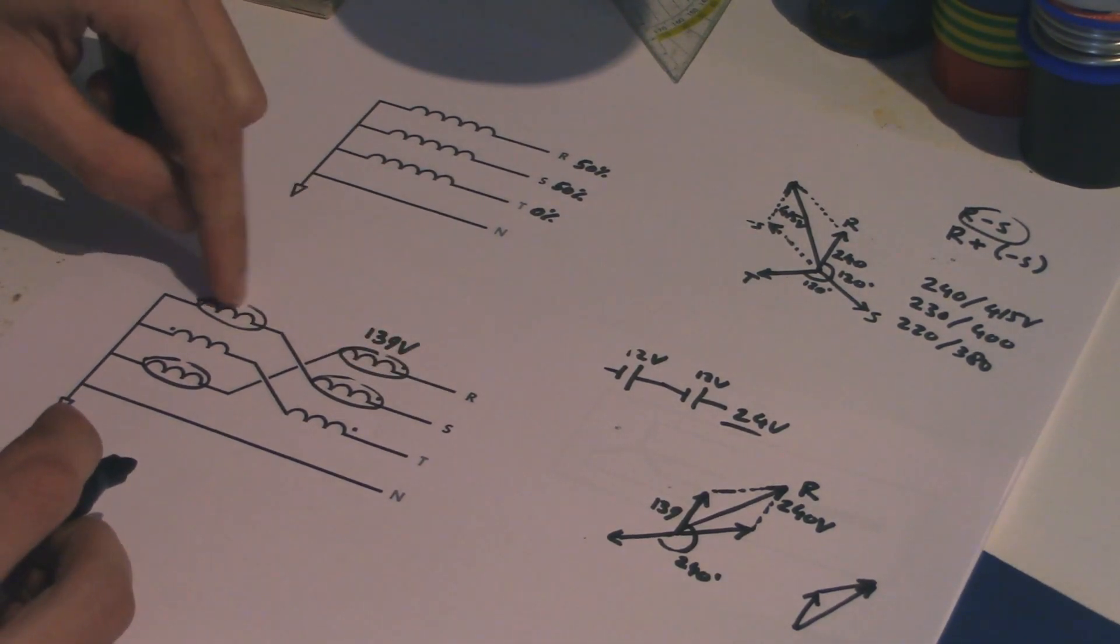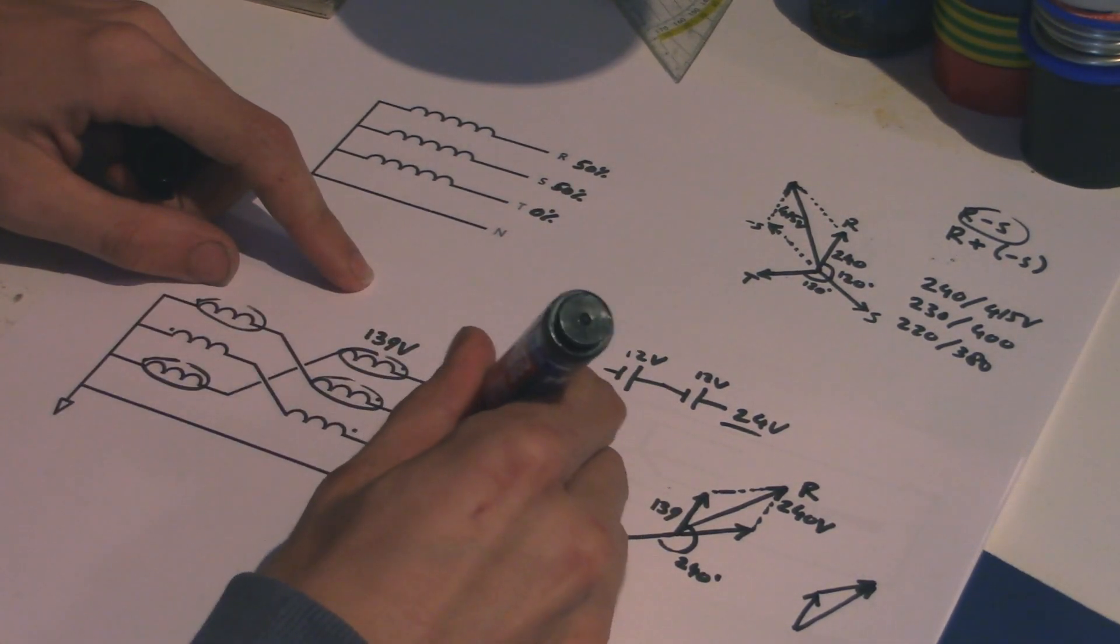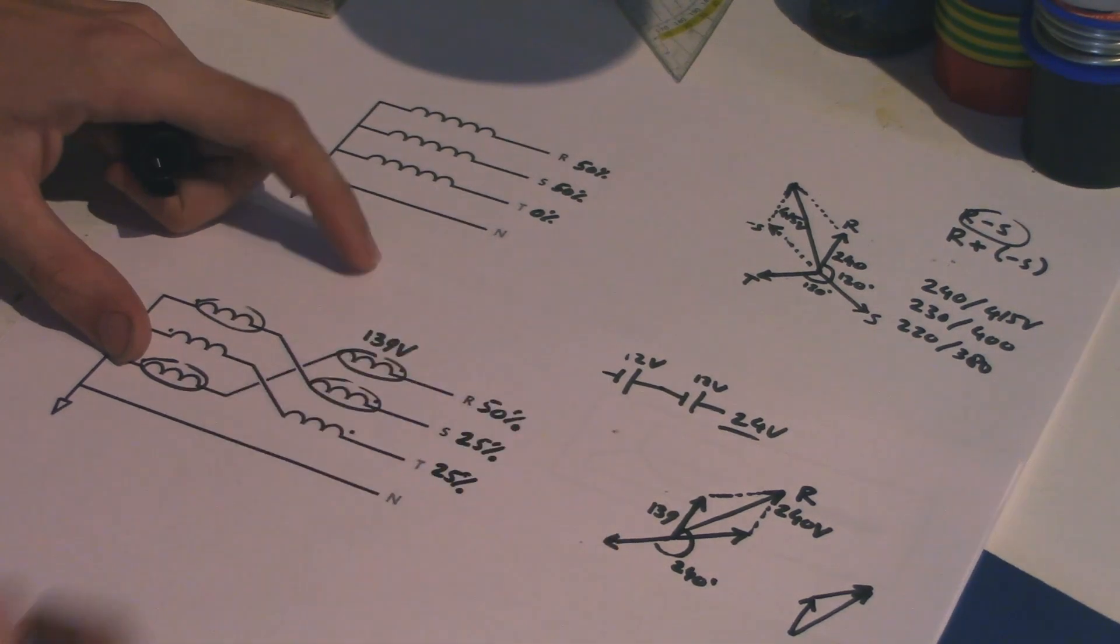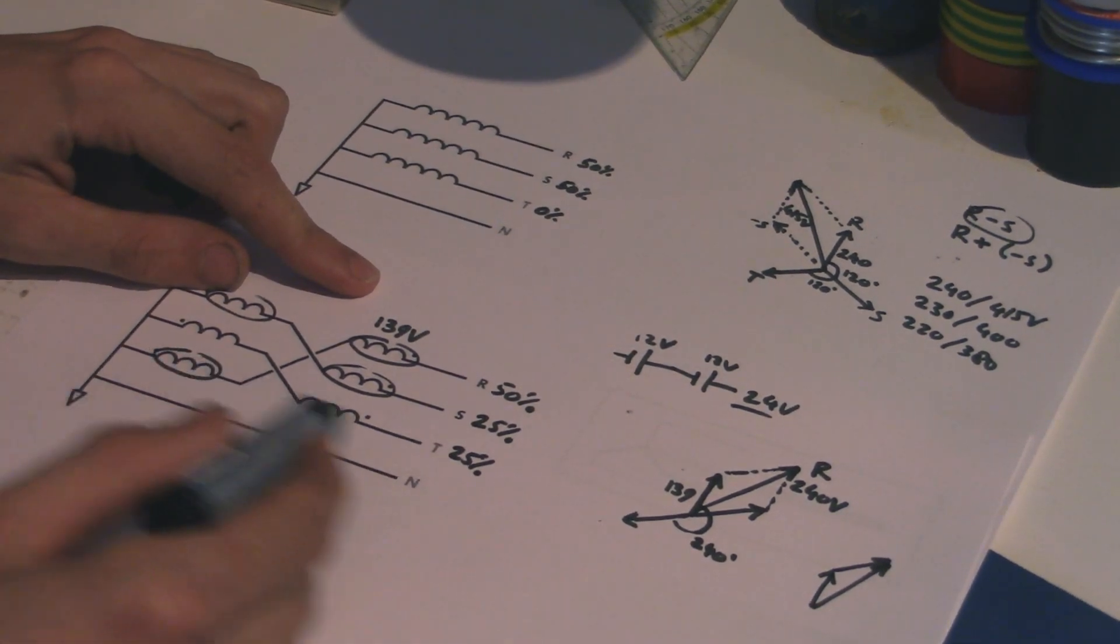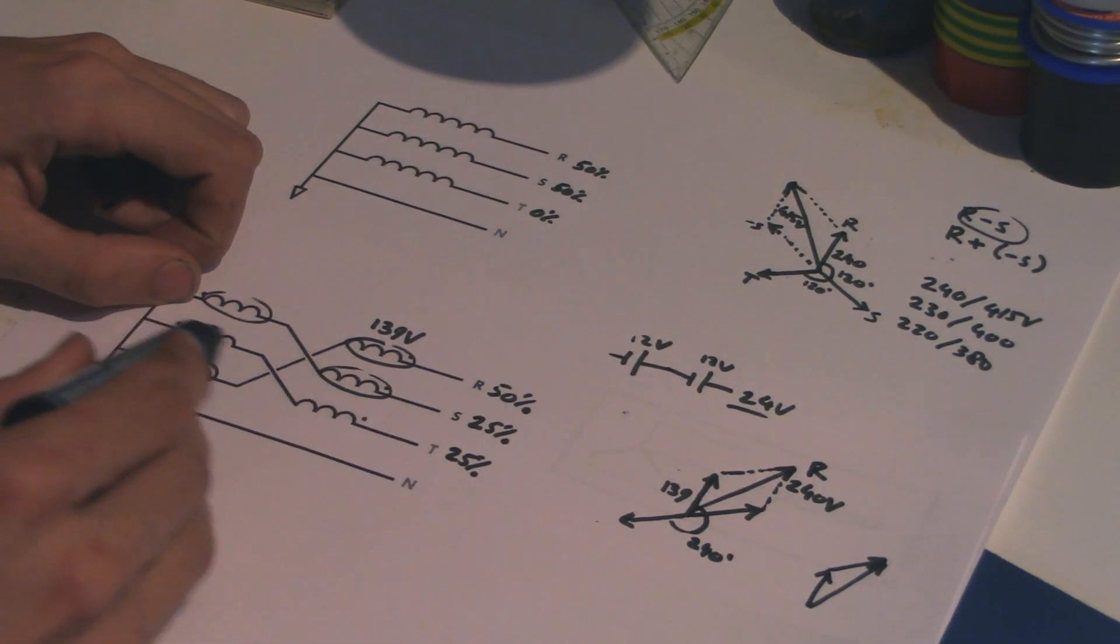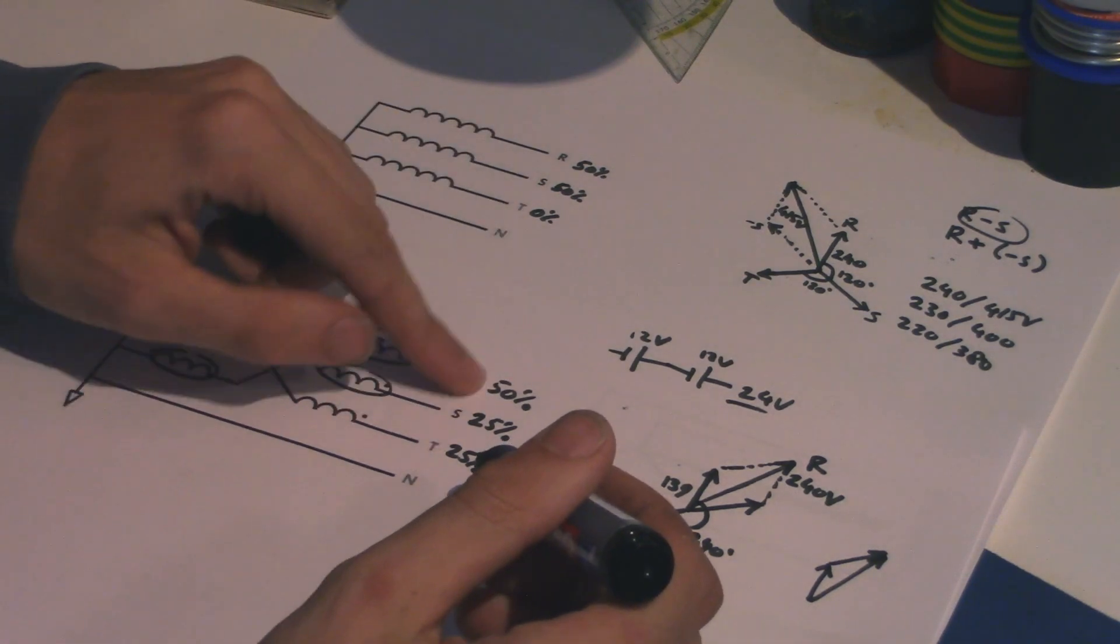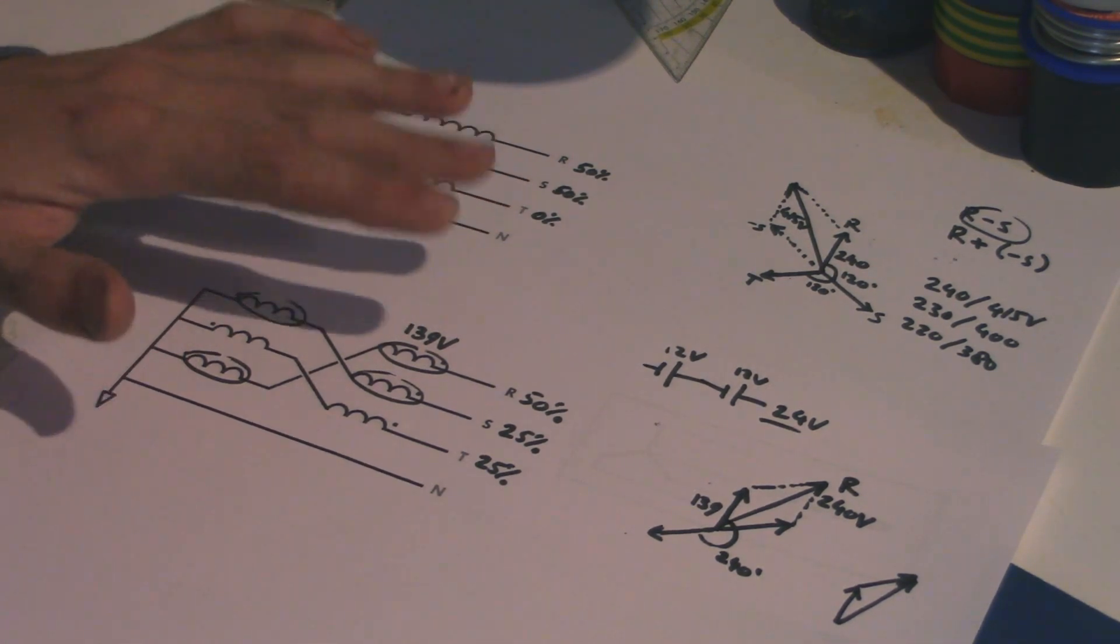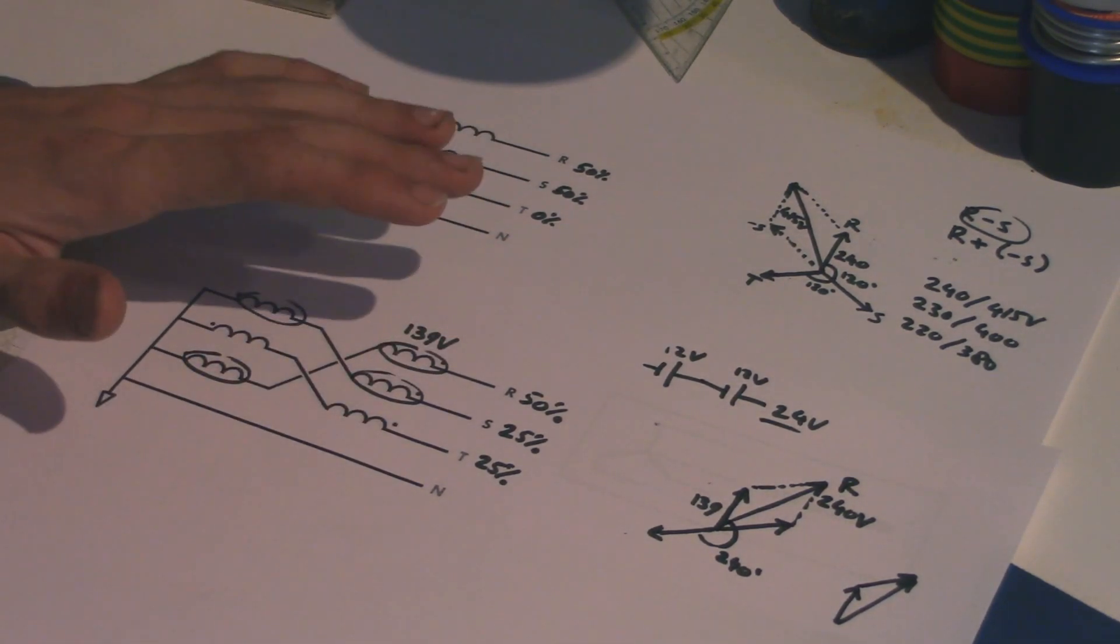Well, it means we have 50% of our load on this leg, but we have 25% of the load on this one, and another 25% on this one. So because of this weird arrangement of these coils, we've now put load on this leg of the transformer, even though we're not even using that phase. And in the process, we've removed some load from this leg of the transformer. So what this does is it kind of spreads out that load a bit better. So that's why you use a transformer like this.